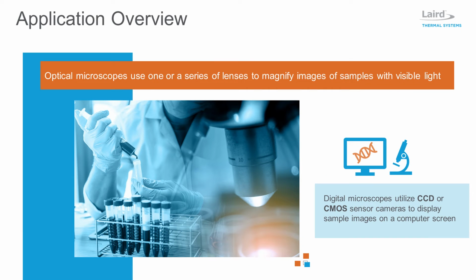In optical microscopes, light travels through a lens to enable a magnified view of a sample. Digital microscopes utilize a CCD or CMOS sensor-based camera to focus on a sample and display the image on a computer screen. Because high temperatures increase thermal noise and negatively affect image resolution, CCD or CMOS sensors need to be kept below ambient, depending on the type of microscope.